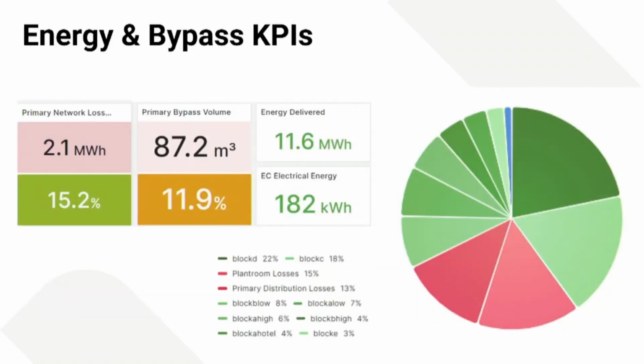Energy and bypass KPIs. So this is quite a big one. This comes out of getting your metering infrastructure in place. So where's all the energy go? What are your losses? What's your electrical consumption? So these come out of your BMS systems now. Primary network losses and bypass flow. Being able to put figures on it helps us identify things like the main bypass valve was leaking and letting by. But you get a figure now. You can go and change it. You can see the figure change, and you're actually fixing things.